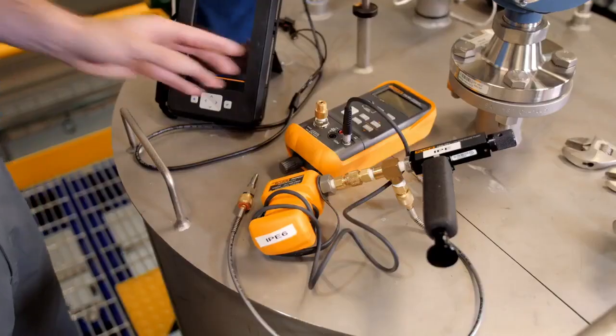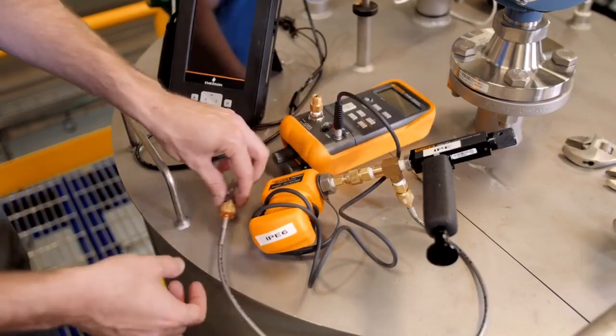We'll start by calibrating the differential pressure sensor, also known as a DP sensor. It's important that the DP sensor be calibrated at line pressure to negate any line pressure effects. The first step will be to connect a pressure source that is at least three times as accurate as the transmitter.